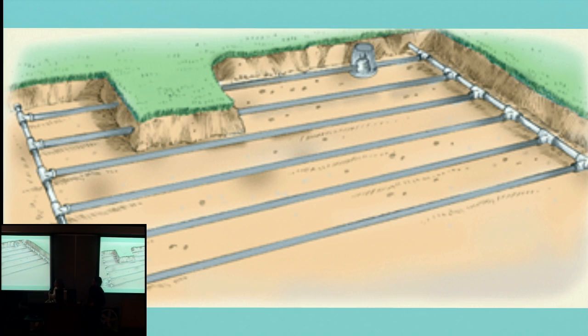And then we want to check that they have air relief valves if those are required, and that's what this is down here. When they turn the system on, you can open that valve box and see the air relief valve release air. You want to make sure that's working and that it's not leaking. Oh, by the way, the air relief valve also has to be on the highest point of the circuit. If it's not on the highest point, then they need to take it out and put it in the highest spot. And then the flush valve is usually at the lowest spot or at the farthest spot.